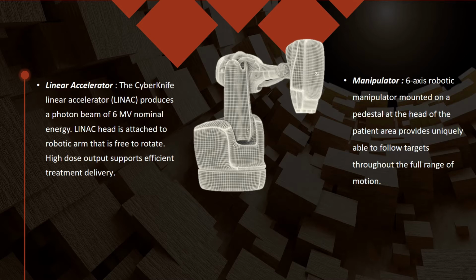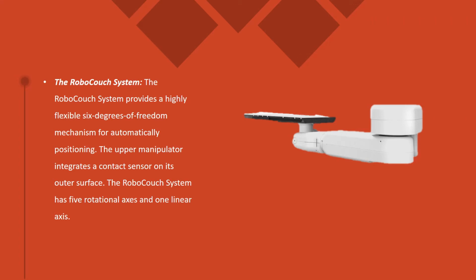And manipulator. The 6-axis manipulator, mounted on a pedestal at the head of the patient area, is uniquely able to follow targets through the full range of motion with sub-millimeter accuracy and precision. The RoboCouch system provides a highly flexible 6 degrees of freedom mechanism for automatic positioning. The combination of the RoboCouch system and the robotic manipulator for Linac positioning enables the Cyberknife treatment delivery system to deliver the dose precisely and to the right location automatically. The upper manipulator arm between axis A2 and A3 integrates a contact sensor on its outer surface, and motion is stopped if an object comes in contact with it. The RoboCouch system has 5 rotational axes and 1 linear axis.